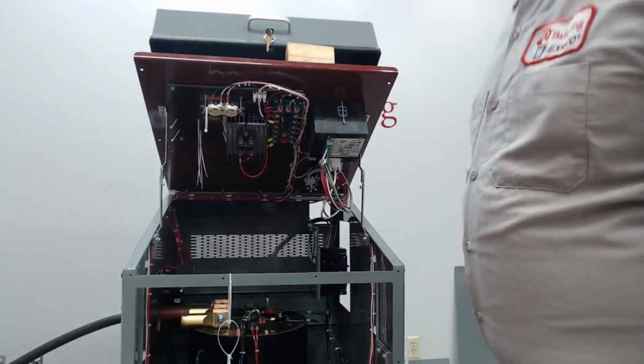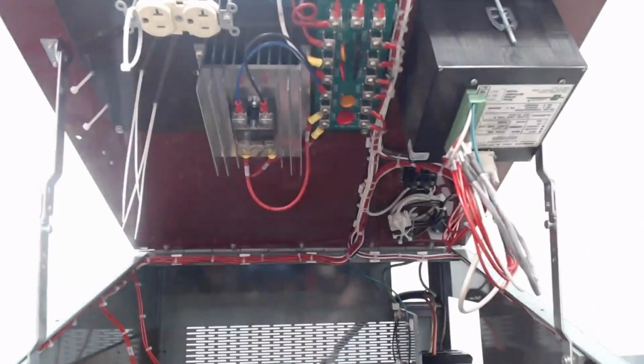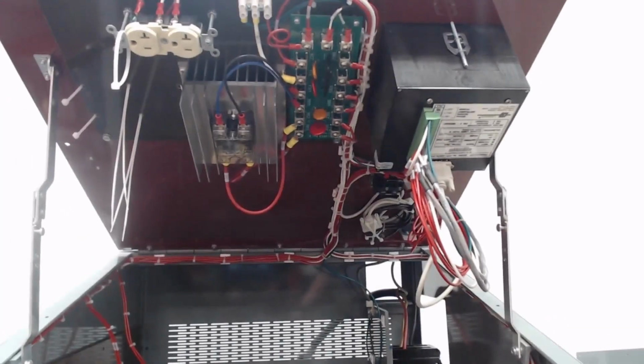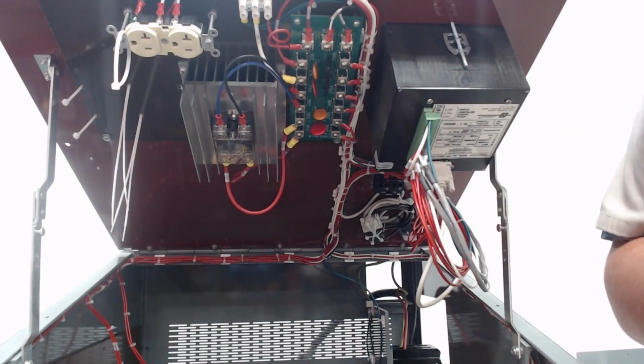All right, we're going to bring this closer. All right, hopefully I didn't disorient you too much. So what we're going to do is, you're going to need a multimeter, preferably one with a min-max feature so you can take instantaneous readings, and it can possibly pick up the inrush current, both current and voltage drop if that's occurring for you.